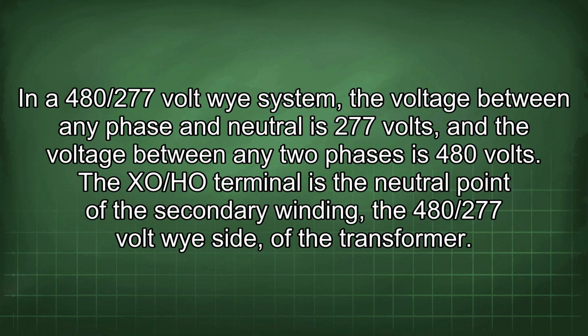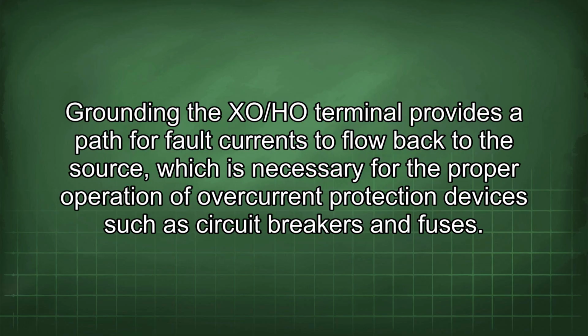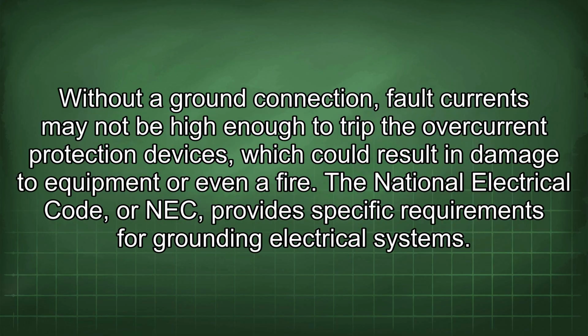In a 480/277 volt Y system, the voltage between any phase and neutral is 277 volts, and the voltage between any two phases is 480 volts. The XO/HO terminal is the neutral point of the secondary winding, the 480/277 volt Y side of the transformer. Grounding the XO/HO terminal provides a path for fault currents to flow back to the source, which is necessary for the proper operation of overcurrent protection devices such as circuit breakers and fuses. Without a ground connection, fault currents may not be high enough to trip the overcurrent protection devices, which could result in damage to equipment or even a fire.